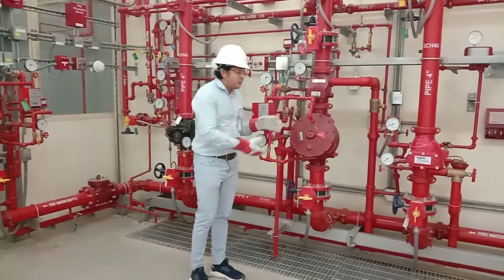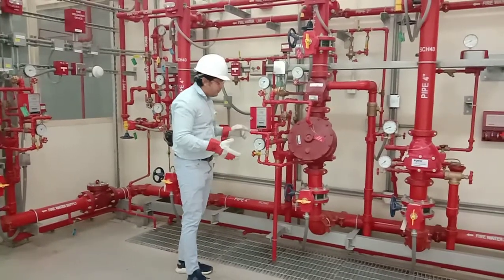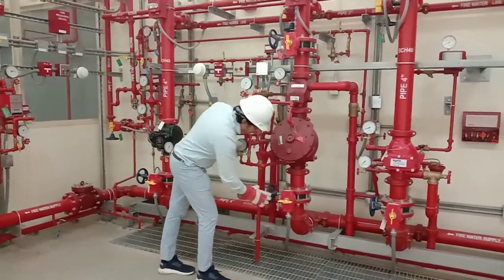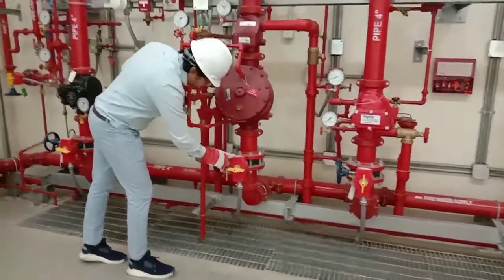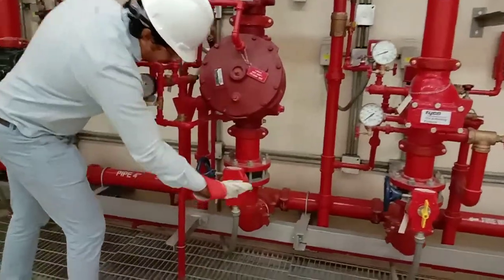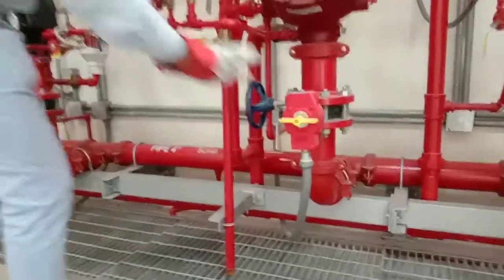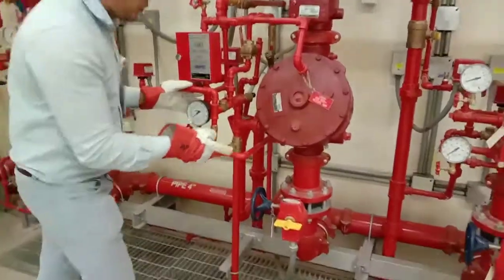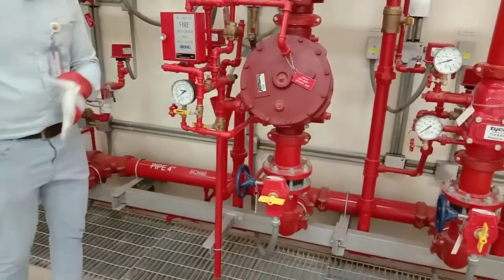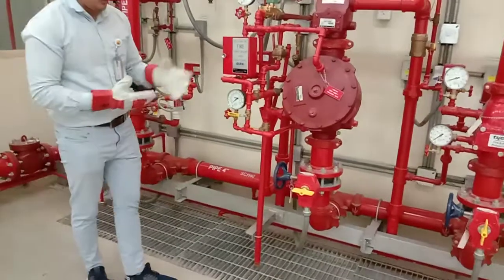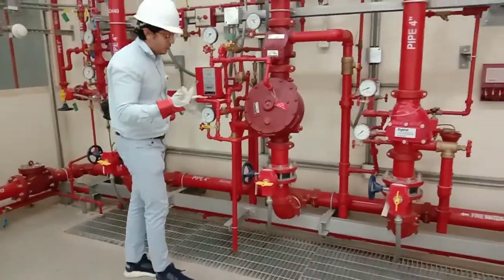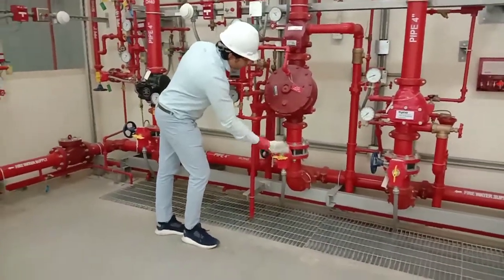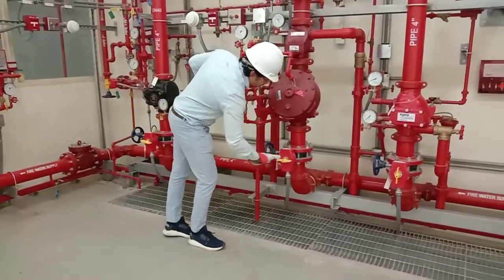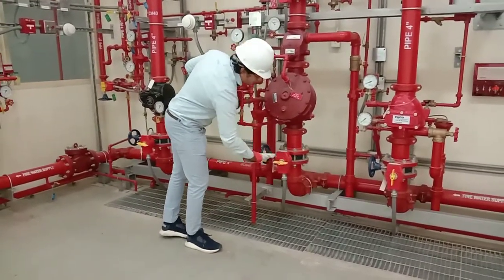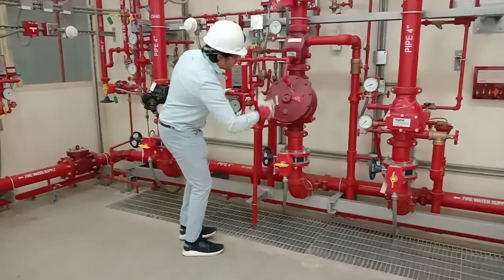Now coming to the different components of the pre-action system, we have a control valve, right? It's a butterfly valve made by NIBCO. If you can see this one, it is an indicating type, meaning the valve is closed at this moment. Keep in mind this should always be open 24/7, 365 days, but since this is our lab for training purposes, we are just showing our participants various simulations. So if you turn this one, the valve opens and closes. At this moment, the valve is closed because it is perpendicular to the pipe. If it is parallel to the pipe, the valve is open.